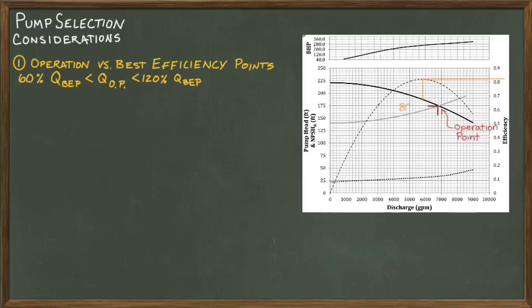On this chart, the BEP is located by drawing a line vertically from the max efficiency point on the curve to the pump performance curve. The corresponding flow rate is read from the x-axis. In this example, the Q_BEP is 5800 gallons per minute.